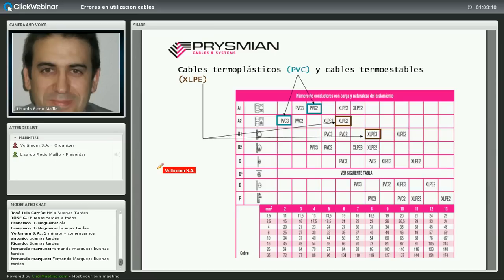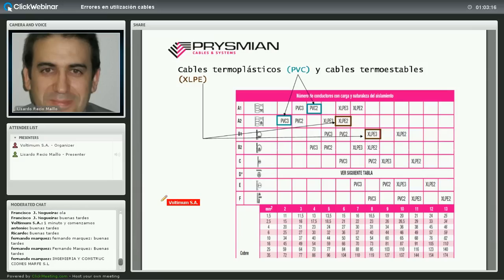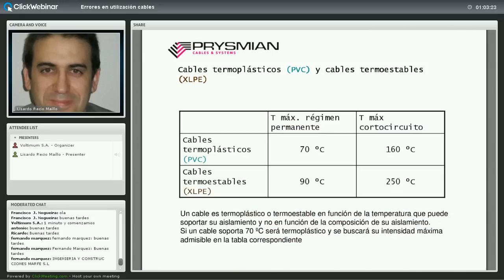XLPE y PVC: esta abreviatura no es del todo acertada pero trata de cómo se comportan térmicamente los cables. PVC son cables que pueden soportar hasta 70 grados en régimen permanente y XLPE los que pueden soportar hasta 90 grados en régimen permanente. La designación no es muy afortunada porque puede hacer pensar que se trata de cables aislados con PVC o XLPE, pero realmente puede ser cualquier tipo de cable que se comporte térmicamente de esa manera.